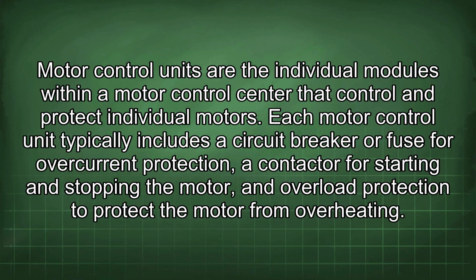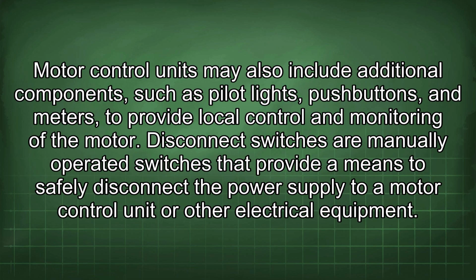Motor control units are the individual modules within a motor control center that control and protect individual motors. Each motor control unit typically includes a circuit breaker or fuse for overcurrent protection, a contactor for starting and stopping the motor, and overload protection to protect the motor from overheating. Motor control units may also include additional components such as pilot lights, push buttons, and meters to provide local control and monitoring of the motor.